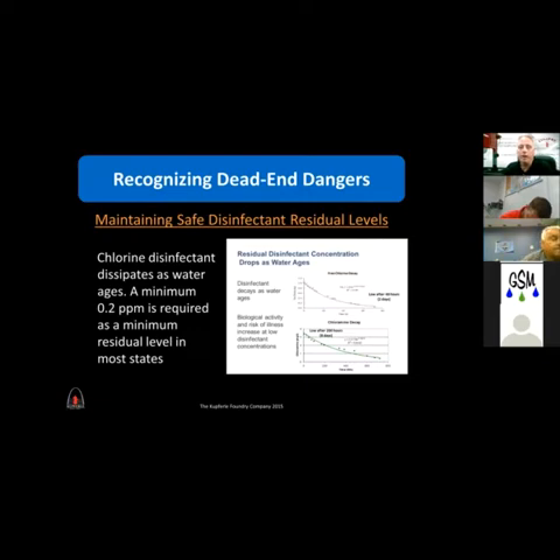But if you look at this chart, a good yardstick for water quality, especially on a dead-end main, is about 4 to 7 days, about a week. Chlorine dissipates at a rate of about 1.5 ppm per week after about the first initial 200 hours. So free chlorine stays in the water pretty well, about 200 hours, and then it dissipates very quickly.